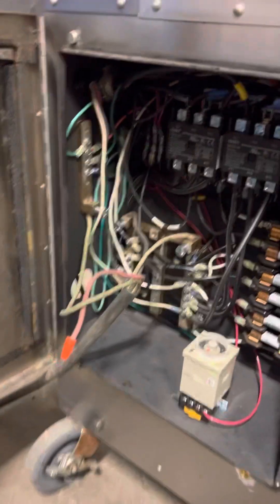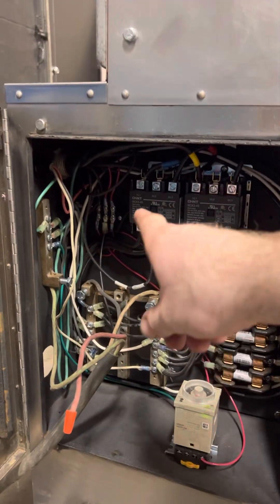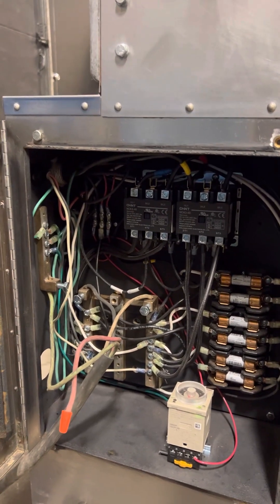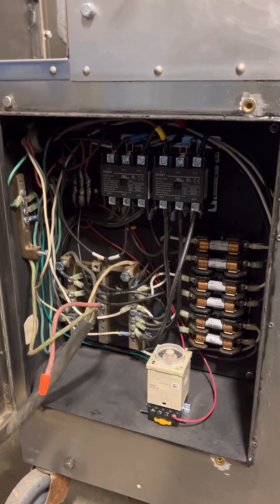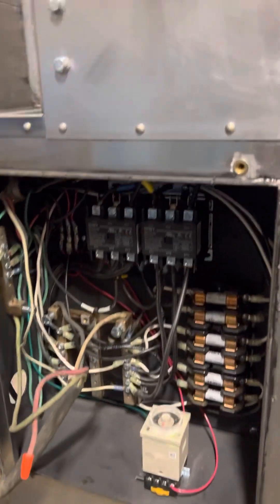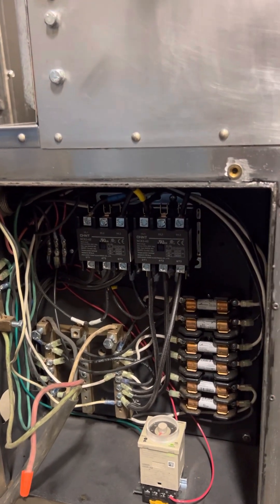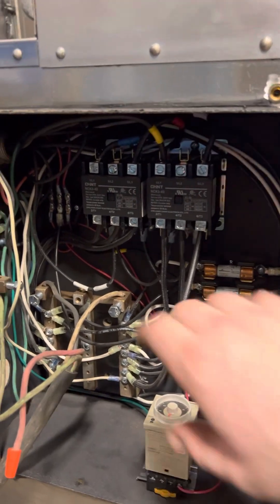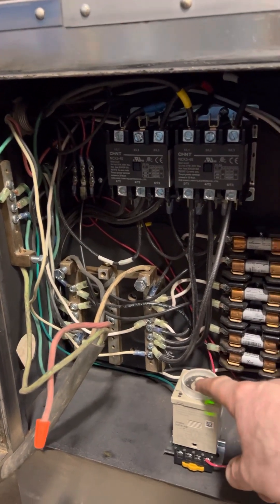In the box here you have 100% brand new wiring — all new wire pulled through all the conduit. There's no such thing as just replacing things wire for wire. The electrical system is completely re-engineered brand new, so there's nothing OEM about this except raw pieces like a thermostat and conveyor bushings. Brand new contactors, all new fuse block and fuses, signal relay.